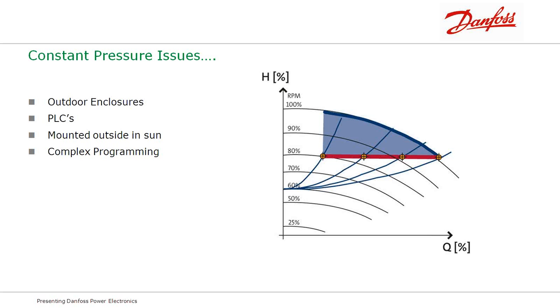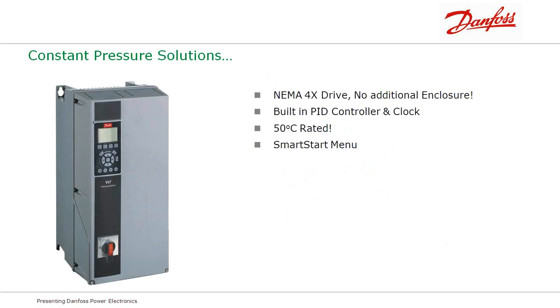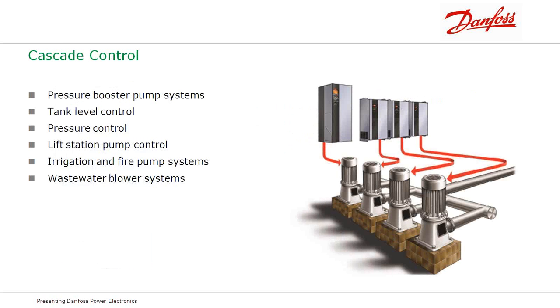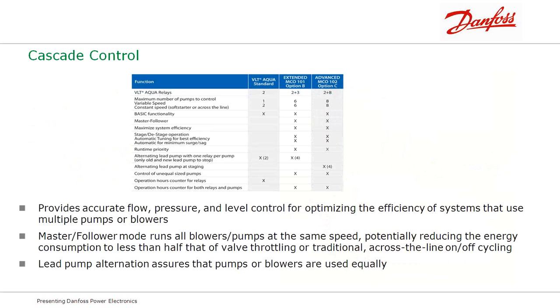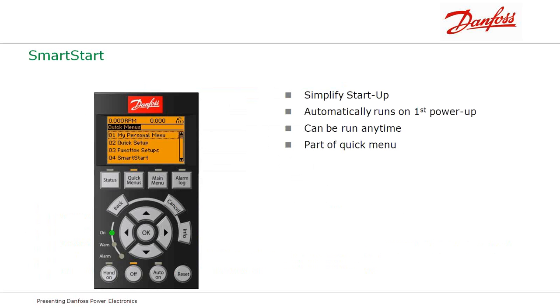Constant pressure, that's a word we're hearing a lot in the irrigation, the agricultural market, on smaller applications. Constant pressure solutions utilizing variable frequency drives. Our drive has a PID controller, so you put a pressure transmitter in the line, and it maintains constant pressure in the system. It can be mounted outdoor, and it can also be used in parallel systems, utilizing the cascade controller that you see here. The drive by itself, without additional PLCs, can maintain up to 8 additional pumps off of one drive, using either variable frequency drives or starters or soft starters to run those.